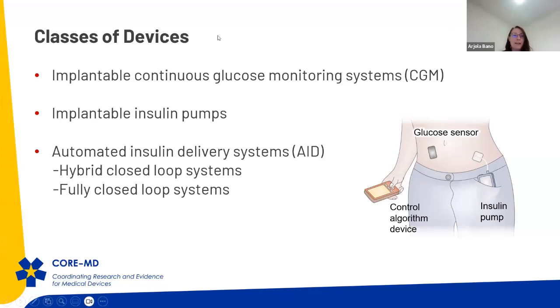The principle of these medical devices in the field of diabetes, especially the automated insulin delivery systems, is based on several components that are crucial in these devices. The first component is the glucose sensor, which is inserted into the skin and senses the glucose levels subcutaneously in the interstitial fluid. Then this information is communicated to a control algorithm device, which, together with additional information based on the personal settings of the patient and the prediction of glucose fluctuations, is then linked to the insulin pump, which delivers insulin in order to keep the blood glucose levels within a target range.